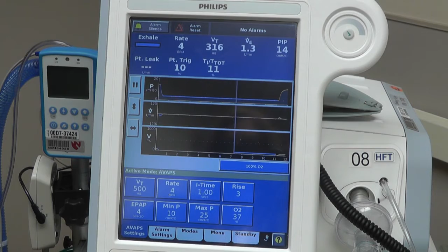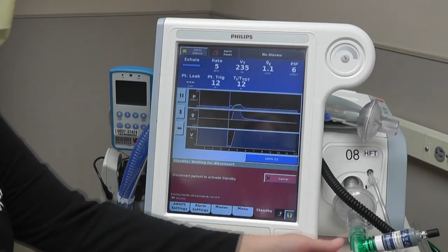So when your patient is ready to come off this machine, whether they're getting up to go to the bathroom or it's in the morning and they're ready to just come off for the day, you don't want to hit the power button to shut it off. You only want to go into standby for the V60. So just hit the standby and it's going to ask you to disconnect your patient. I have a test lung here, so I'm going to disconnect the test lung, but normally you would just take the mask off your patient and it will enter into standby. Every once in a while, just taking your patient off will not stop the machine, and you may have to disconnect here to get it to go into standby. And then it will shift into standby.